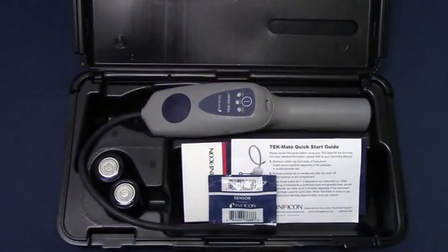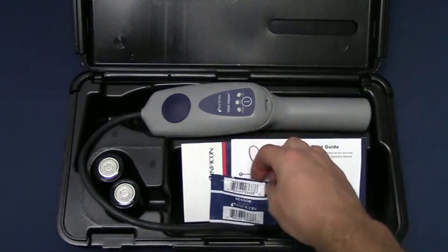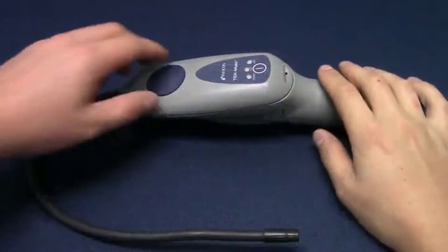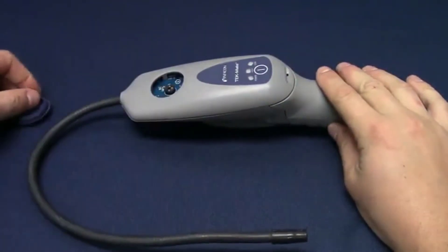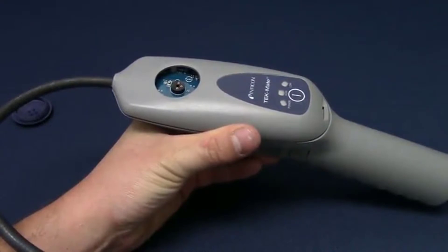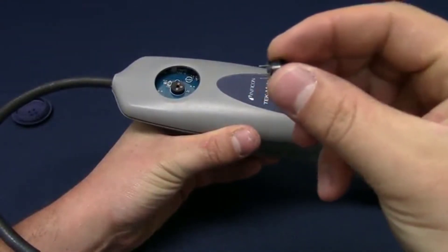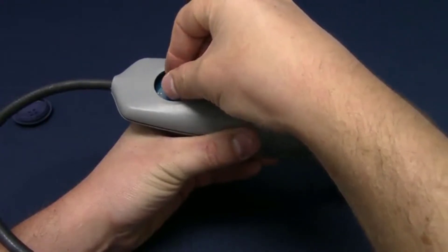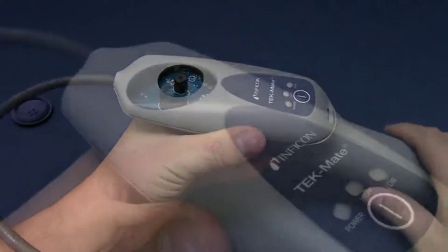All new TechMates ship with a new sensor in a sealed package. A new sensor should last about 100 hours, depending on the application and the exposure to refrigerants. To install the sensor, remove the rubber sensor cover on the face of the TEK-Mate and cut open the sensor package. Be careful not to bend the three small prongs on the sensor during installation and handling. Install the sensor in the TEK-Mate and reinstall the rubber cap.